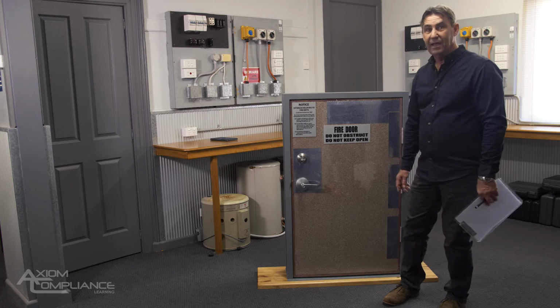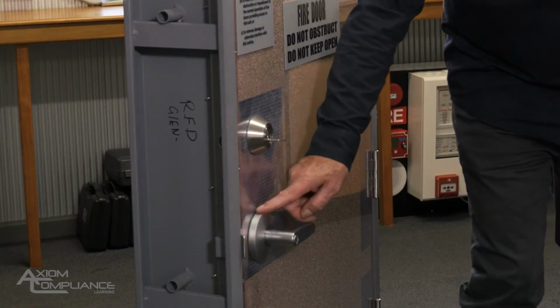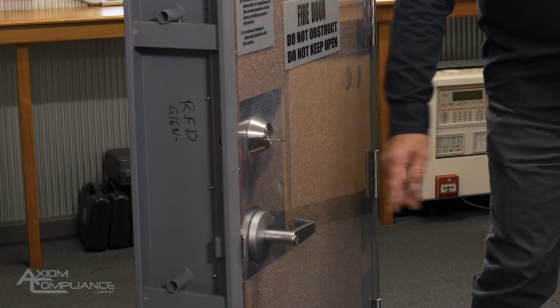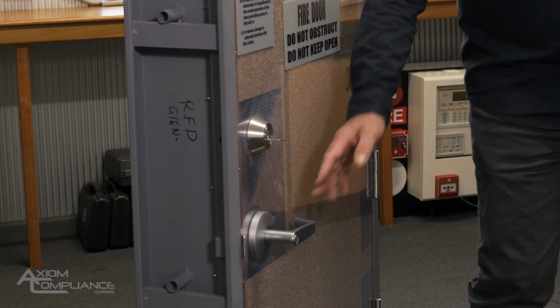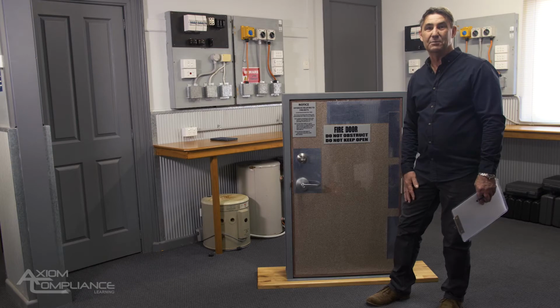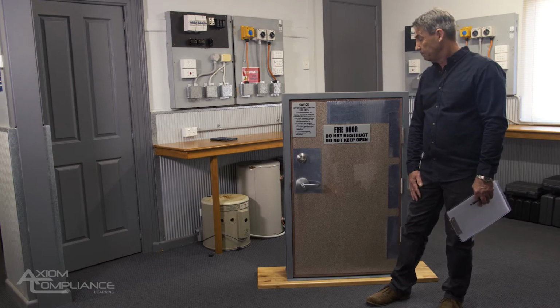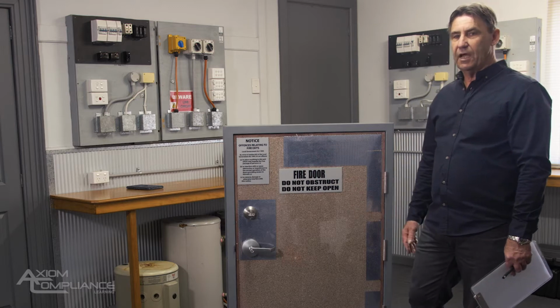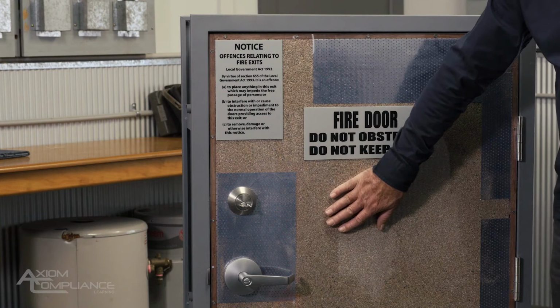And some telltale indicators is generally the door is painted. And so if you see evidence that there is a difference around where the door set probably used to go, and then there's a new set in its place, maybe you've got to investigate whether that door set is compliant or not. So for this particular door set, we've had it made with a clear laminated face.